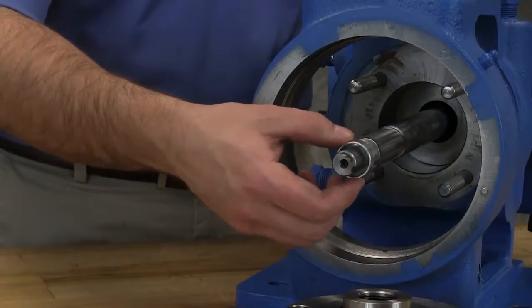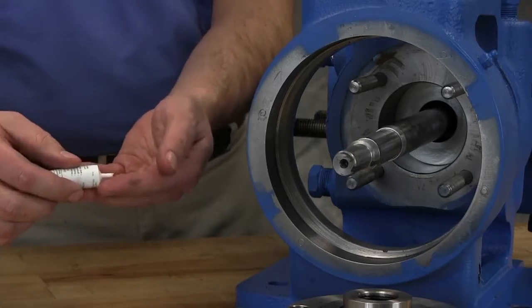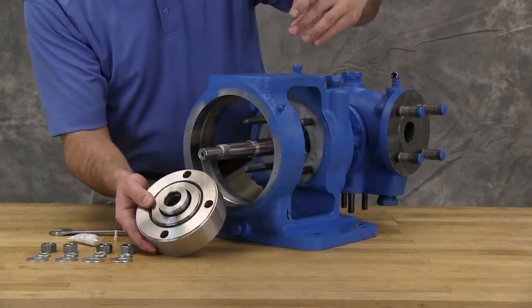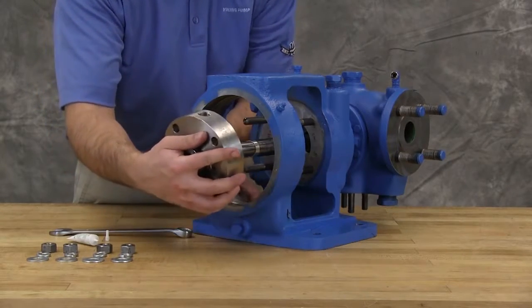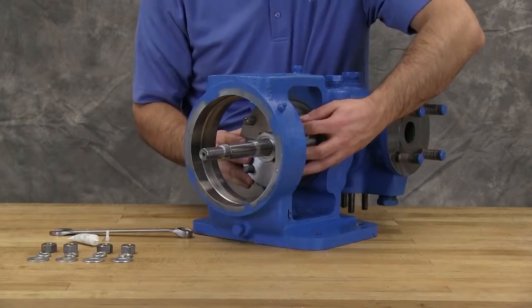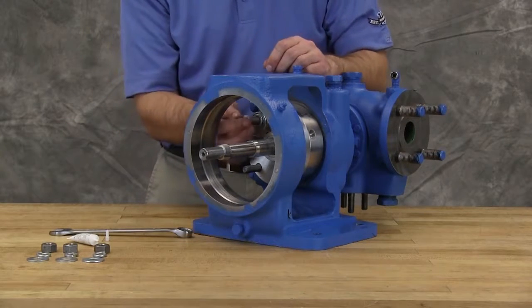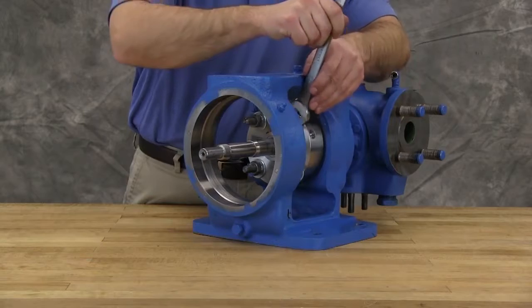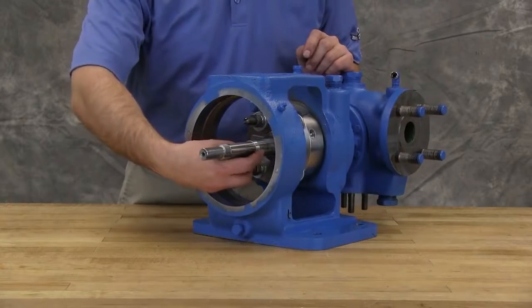Install the tapered installation sleeve on the shaft. Make sure the shaft is free of burrs that could damage the O-rings of the seal. Coat the rotor shaft, tapered installation sleeve, and the inside of the rotary member of the seal with a generous amount of light oil. Install the seal onto the shaft, making sure it is oriented with the flush port at the 12 o'clock position. Secure the gland onto the bracket face using the proper hardware. Tighten only enough to contain leakage and not to distort the seal gland. Remove the seal installation sleeve.